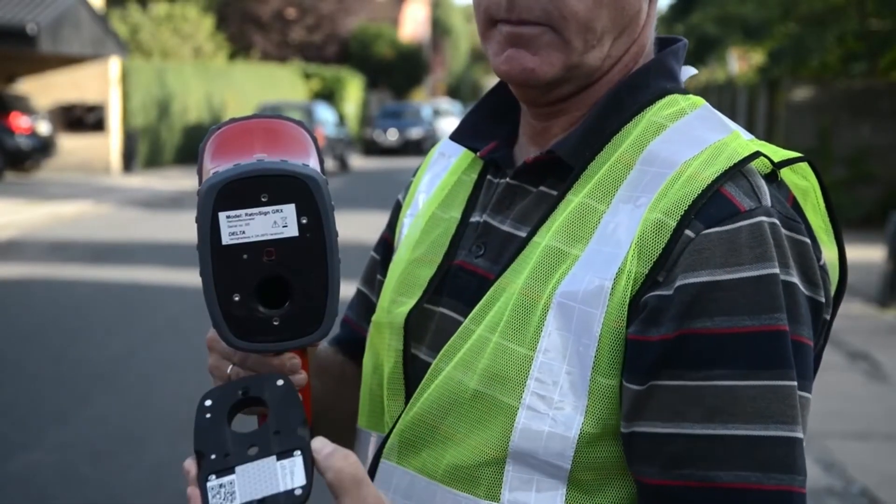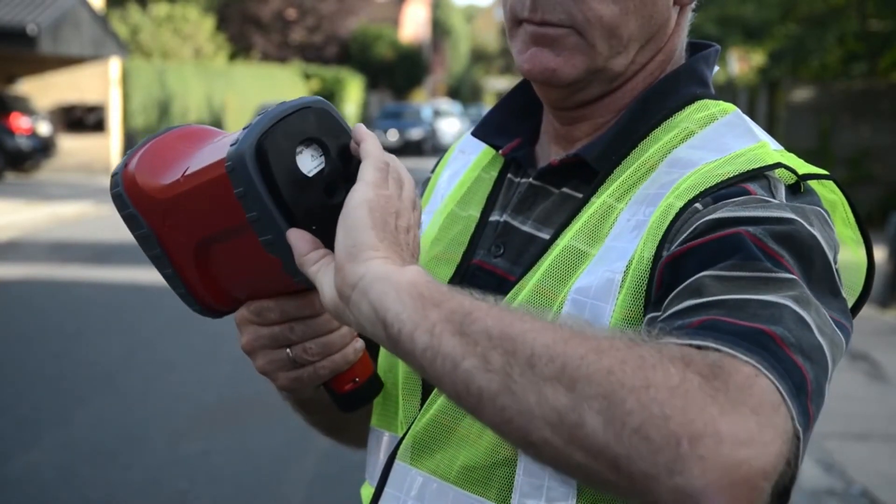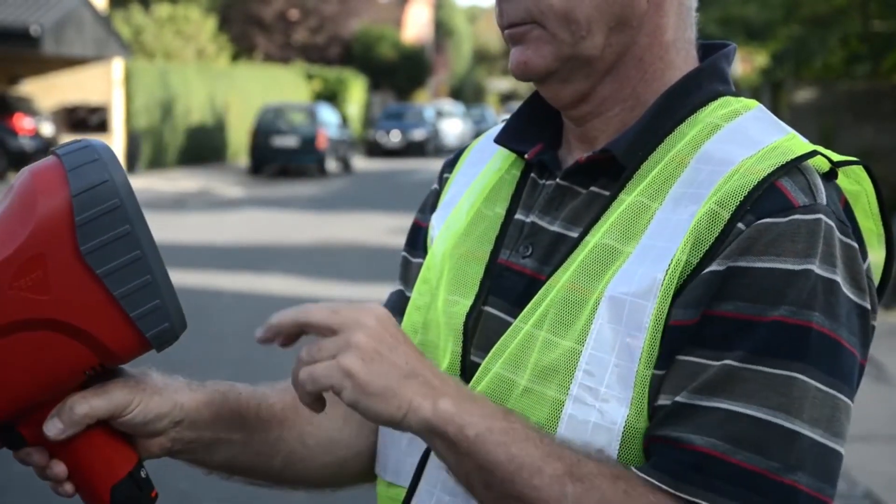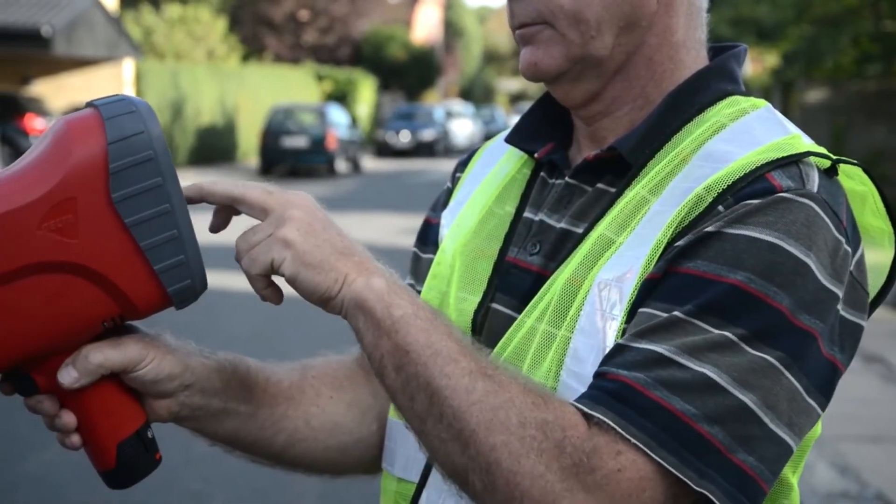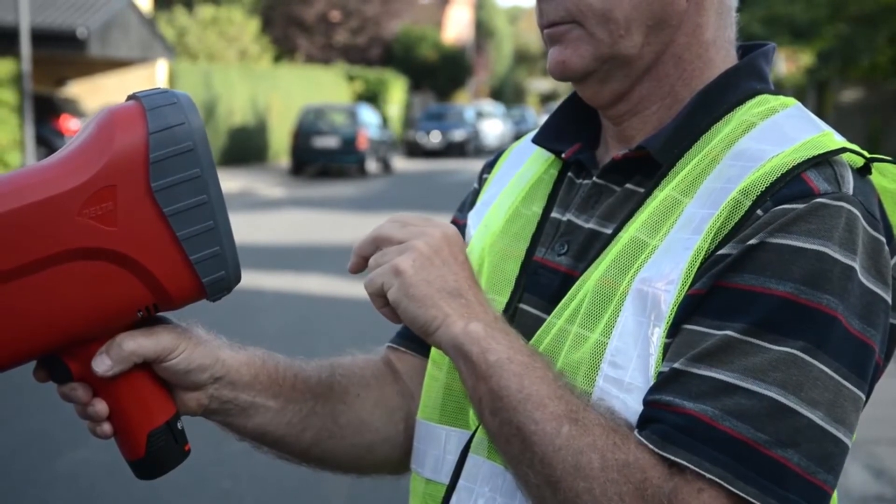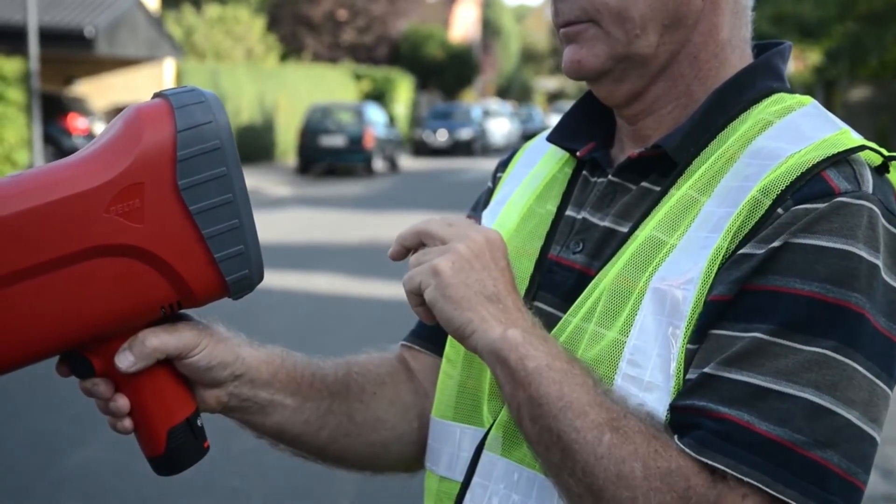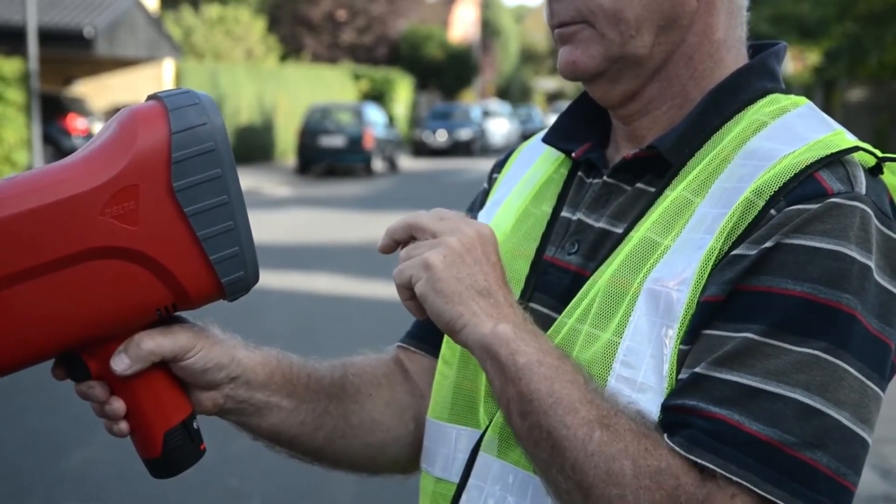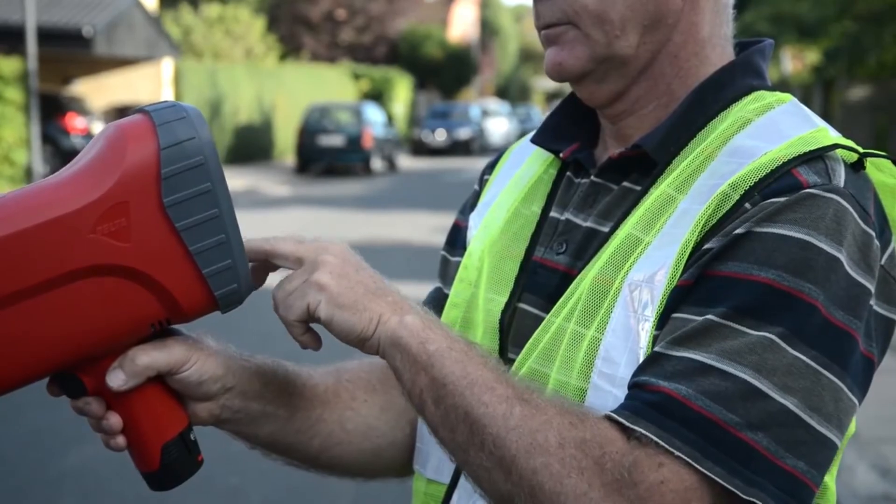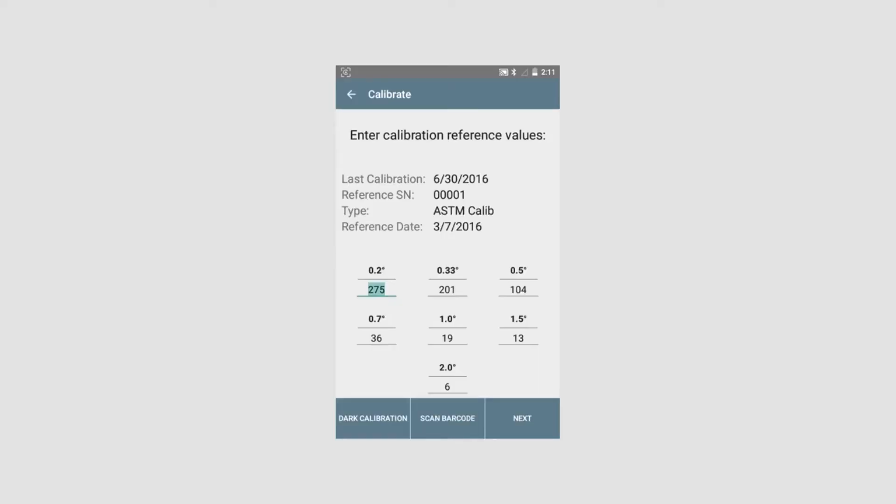Calibration: It's important to make a daily calibration of the instrument to ensure it measures correctly. This is typically done in the morning before measurement is started. There are two ways to start the calibration procedure. One is to type in the figures of the different observation angle as seen on the screen. The other one is to scan the barcode. We will do the scanning of the barcode.